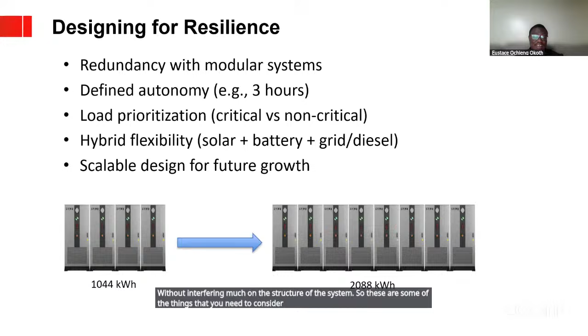And when you look at the sizing, which I think most of the engineers now are aware of, some of the key things that you need to consider at the peak load is: is the inverter able to handle my peak load? Because I've seen a lot of designs where when the customer says my load is 10 kilowatts, the best we can do is to give the customer 12 or 15 kilowatts. Yet we are not looking at the peak load, the surges that comes in with the system.